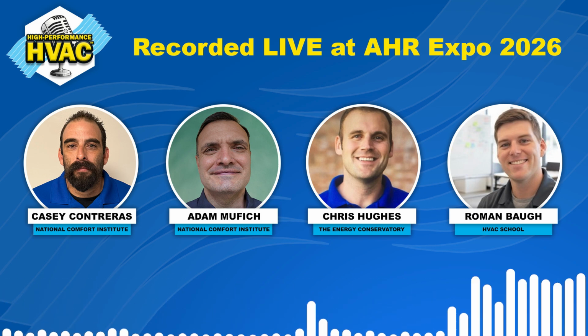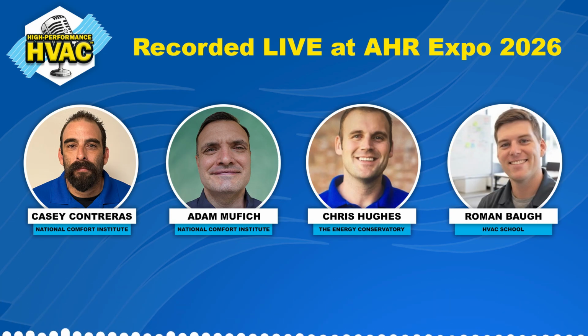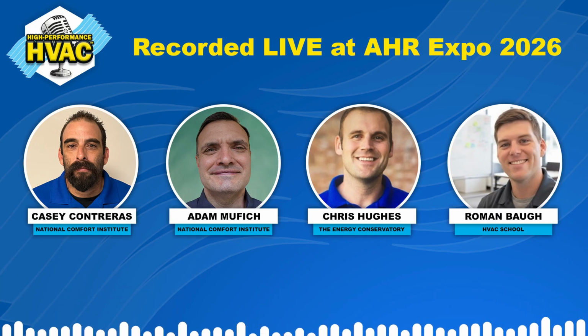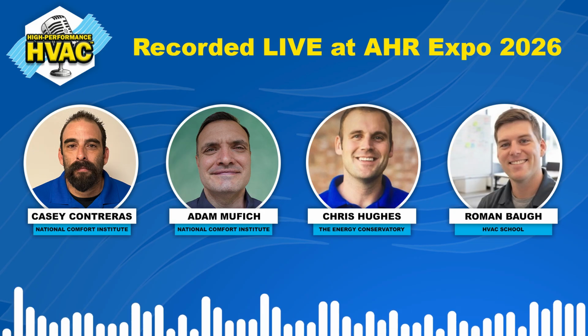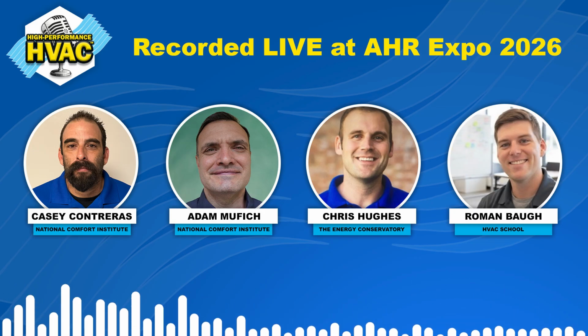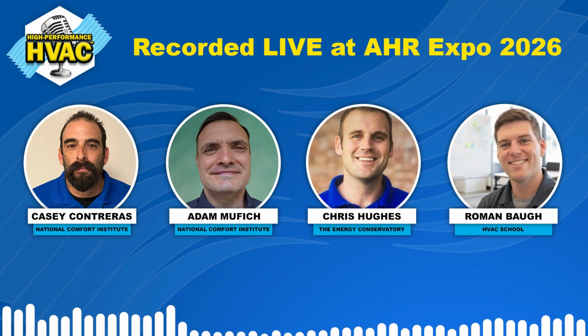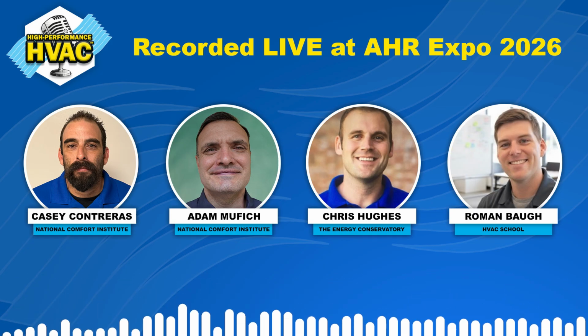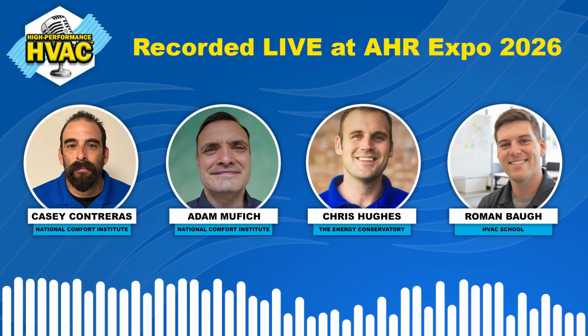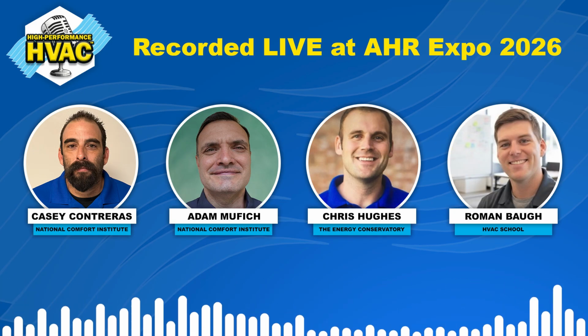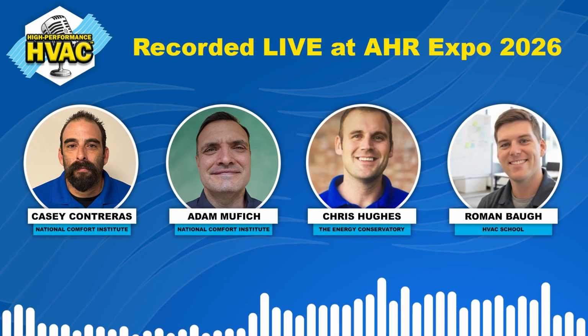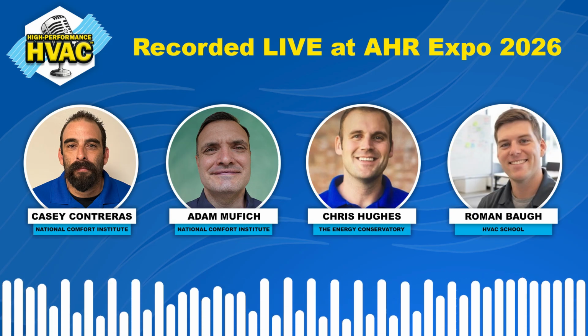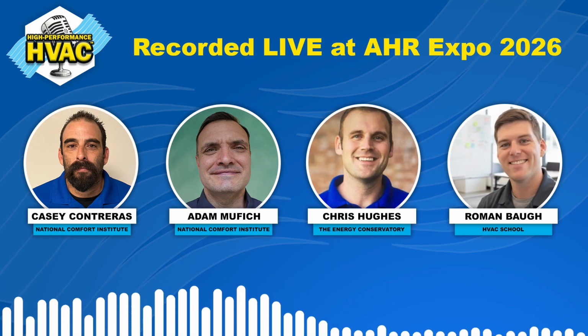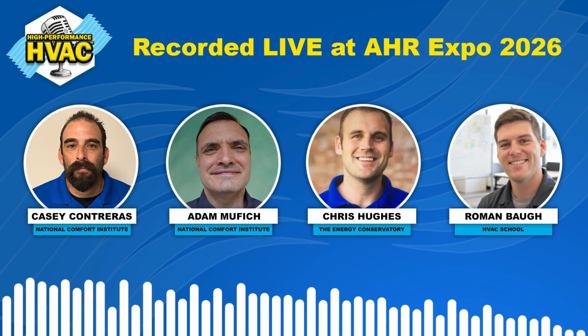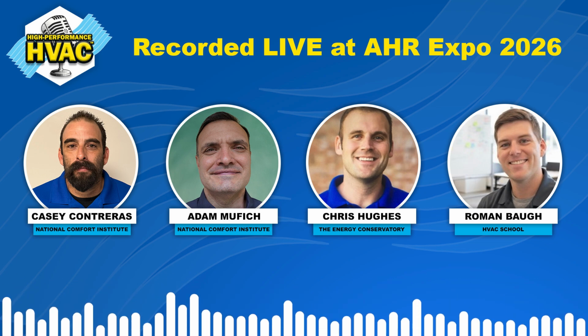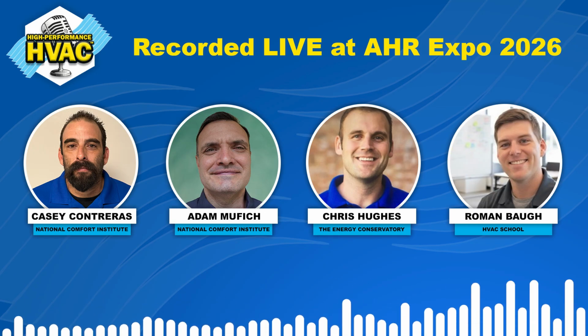And you look at, like you said, there are 3 different metrics you're looking at the entire time. So it's not like a regular, straight cool system where we're at TXV. Obviously, it's in heating, but straight cool AC, TXV, you're looking at subcooling, right? Sure, yeah. You're paying attention to superheat to make sure you have a TXV functioning properly. Correct, yeah. If it's a fixed orifice, you're looking at superheat and subcooling. Airflow's a big one, too. But you're looking at system superheat. So I'm looking at suction superheat. System subcooling. We're running in cool mode. No, heating mode. Heating mode. Okay. I'll do both.